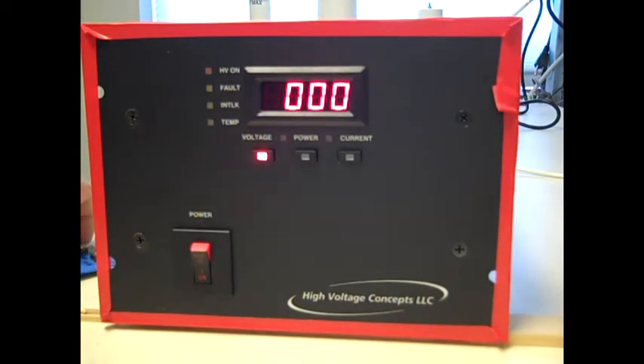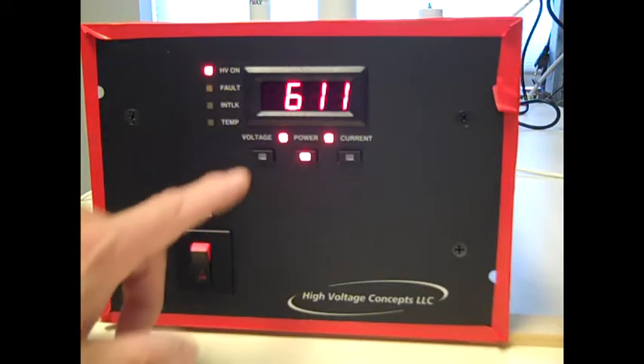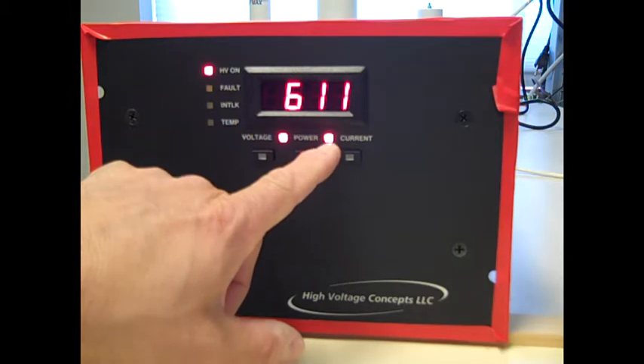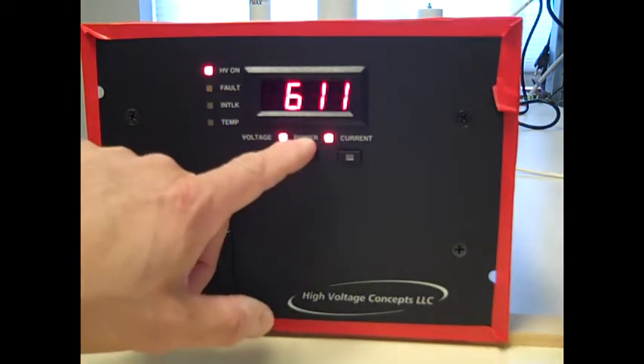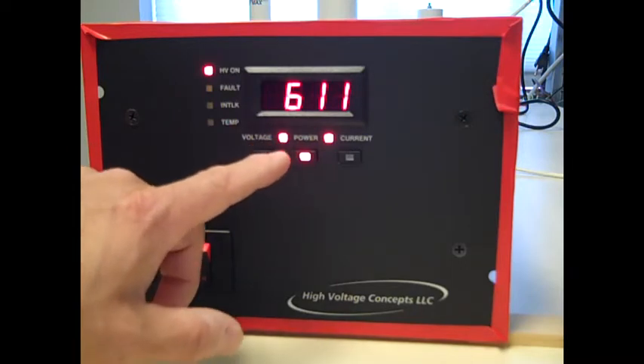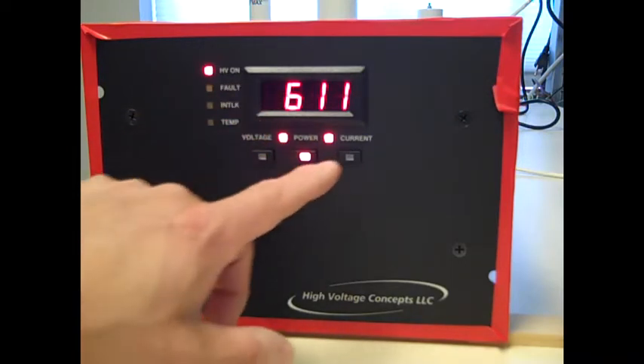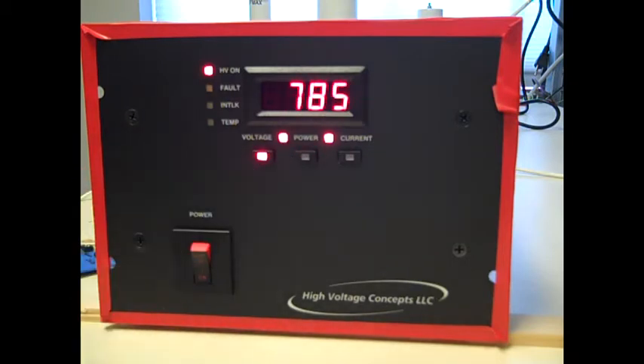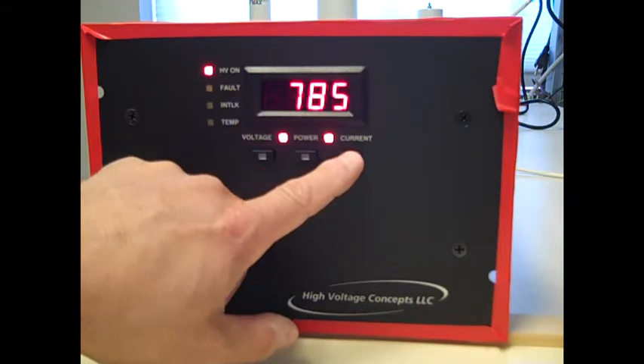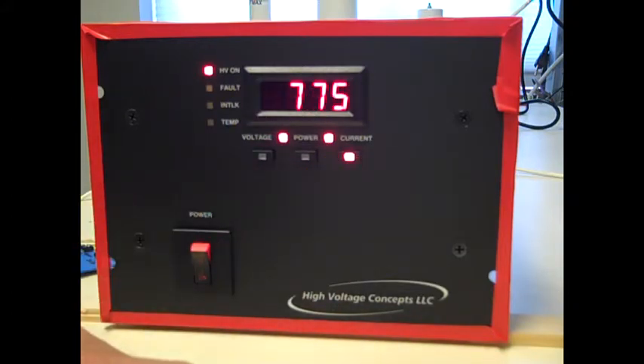Okay, we applied a much heavier load, and now let's go to power regulation, and we're going to turn on high voltage. Now you can see we're at a little bit over 600 watts, and you'll notice that both of these LEDs are lit. When both of these LEDs are lit and the word power is sandwiched by both of those, we're in power regulation mode. So let's look at what the voltage is. Voltage is 785, and let's look at the current. The current is 775 milliamps, and altogether that makes about 610 watts, 611 watts.